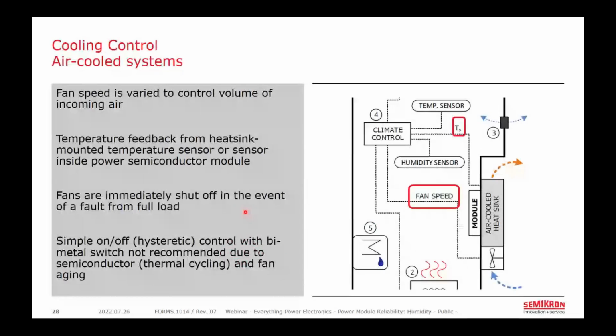So one of the methods we'll talk about here is cooling control. In an electrical enclosure with an air-cooled power converter, we can manage the operating point by monitoring the heat sink temperature here, or even better, the temperature inside the module, and controlling our fan speed. Doing so lets us avoid the condition we talked about in the last section, where a power module is operating at a really high load in a humid environment, and you suddenly shut off the system, and the heat sink is continuing to be cooled. With this setup, we can immediately reduce or stop the fan when there is a quick change in load and avoid that relative humidity overshoot we discussed earlier.